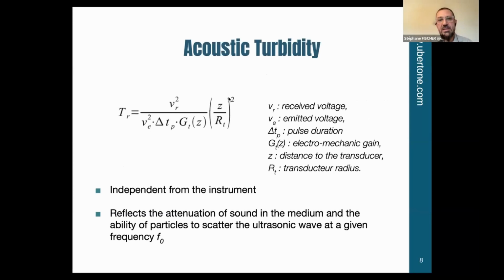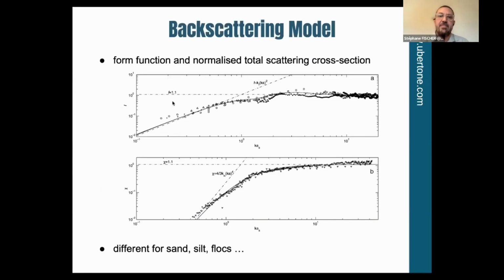We can also define the acoustic turbidity, which is quite a simple expression of the energy we get back from the medium divided by the energy we send into the medium. This acoustic turbidity, which is calculated from the voltage we get from the medium, is a good representative of the scattering of the particles in the medium, and is independent from the instrument. So this is some processing from the voltage that you can get.